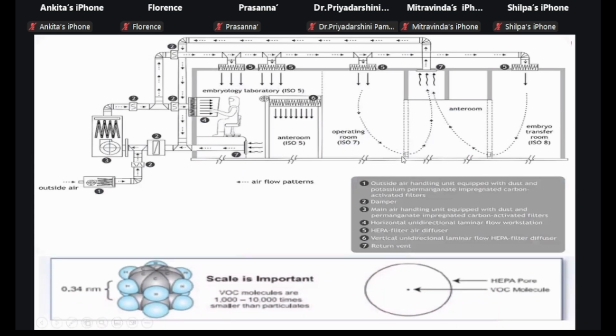This is how the air quality unit is handled. Outside air enters the system and flows through chambers, where there are systems to hinder VOCs from entering the ART lab. The outside air handling unit is equipped with dust filters and potassium permanganate, and is also impregnated with activated carbon filters, so as air flows through these filters, the risk of VOCs entering is decreased.